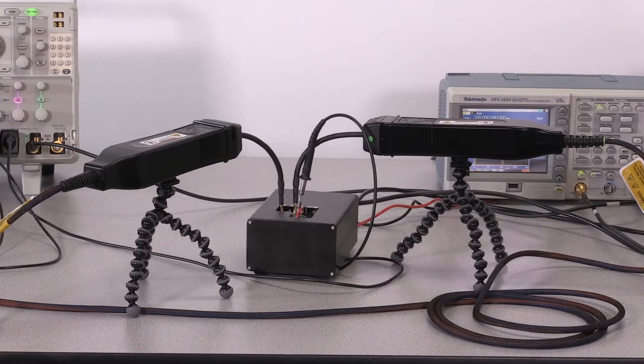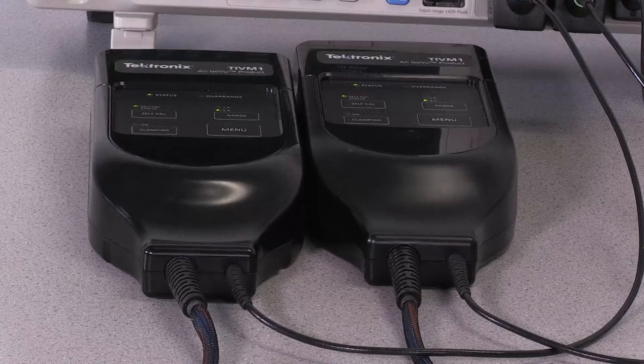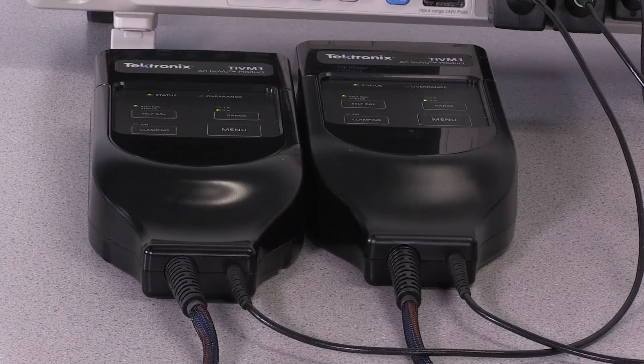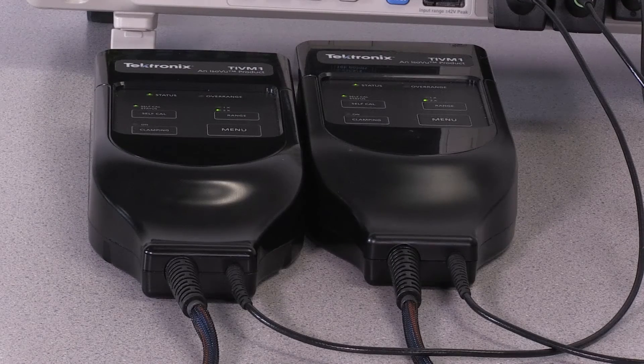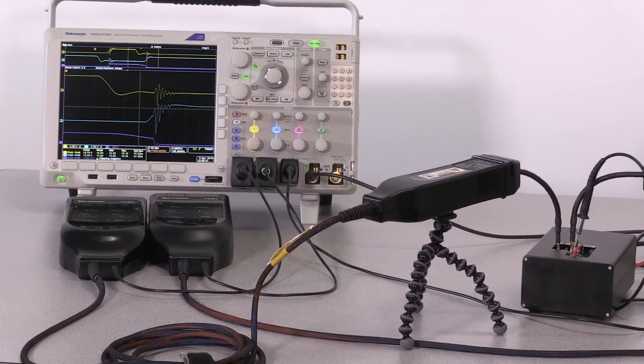With its complete galvanic isolation, the Tektronix IsoVu system has million to one common mode rejection ratio at 100 megahertz. It has gigahertz of bandwidth and 2000-volt common mode rating.